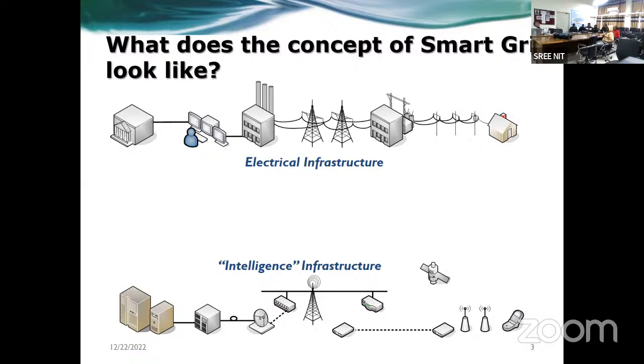Otherwise, in conventional approaches, we first forecast the load, and according to the load forecast, we control our generation. So the load is followed by the generation in the present scenario. But in the future of smart grid, generation is going to vary because of the renewable energy sources, so the generation needs to be followed by the load. So now, according to generation, we have to control the load. In the previous case, according to the load, we were controlling the generation. So that is the difference between the smart grid system and the normal system. So you have to look at this: if you control the load accordingly, you must have a remote control unit also. We must have a remote data monitoring unit also, and we must have prioritization of the load.